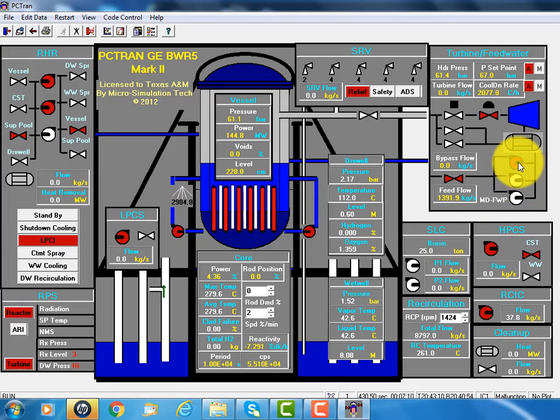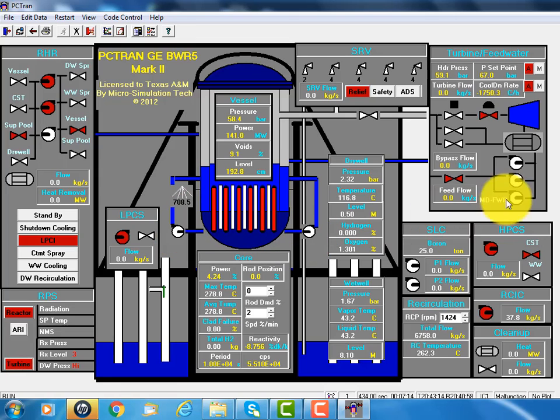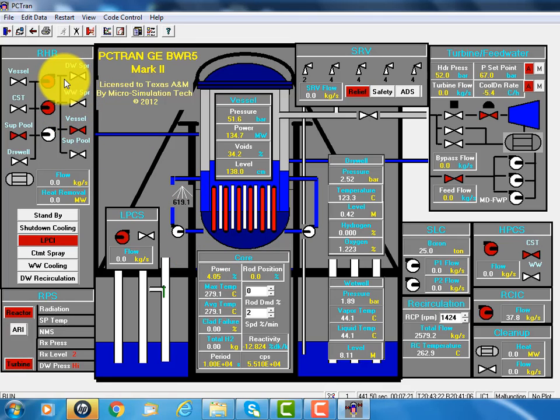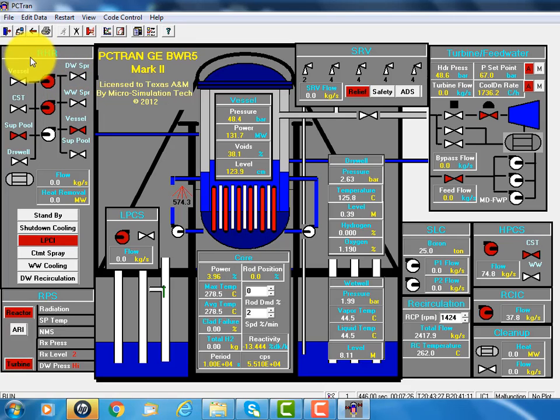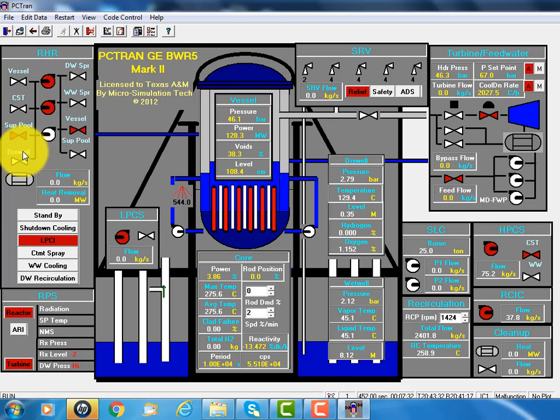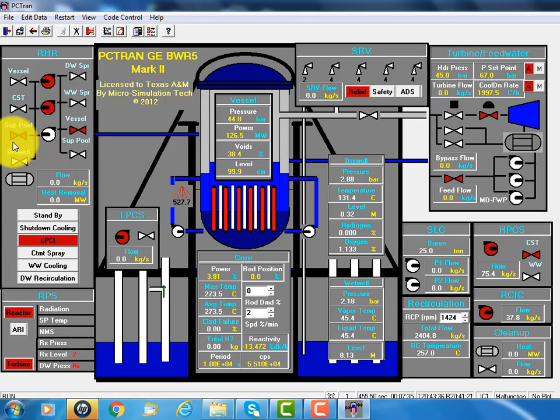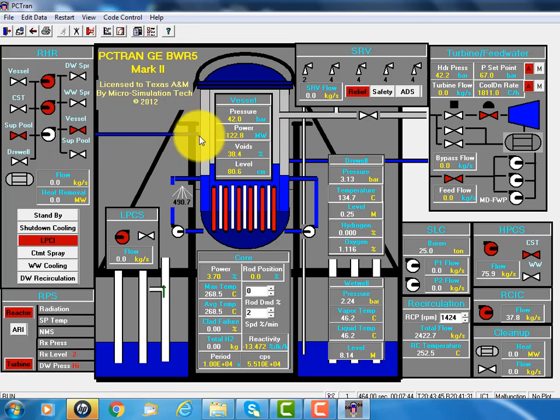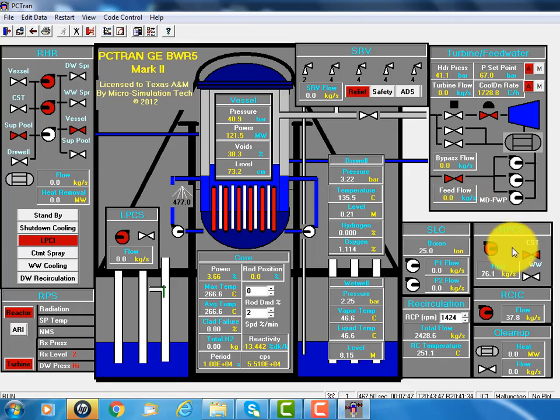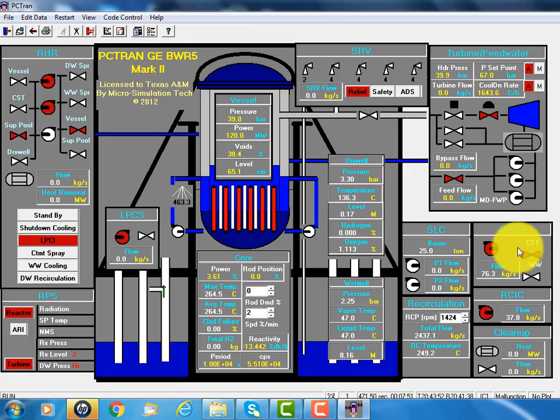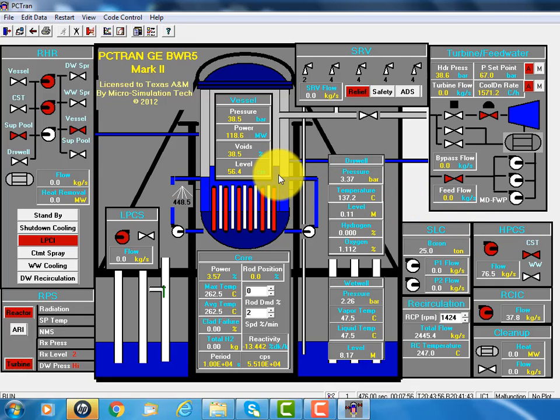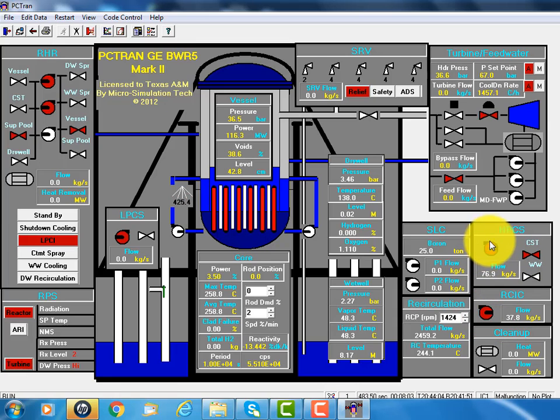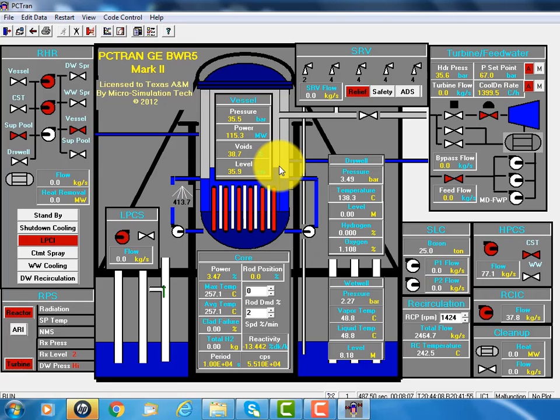Suppose we lose AC power. That stops all the feed water pump and the recirculation pump. The diesel generator or emergency generator will automatically start the low pressure RHR, residual heat removal system. So the coolant will be pumped from the suppression pool into the reactor vessel. There are also high pressure core spray. Suck water from the condensate storage tank and spray on top of the fuel. And there are also reactor core isolation cooling. That's a turbine driven pump to supply. So there are three redundant systems that keep the core covered.